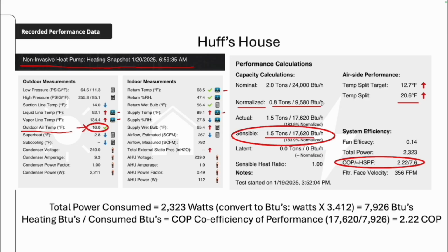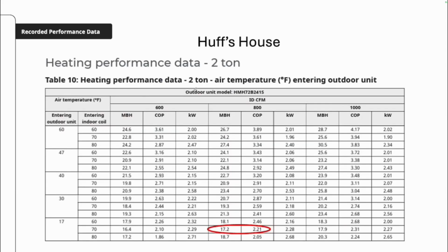And so this is why I'm doing this video. This is why we're talking about literally going back to the OEM's documents. So I'm delivering 17,620 BTUs to my house. Now, my return temperature is 68.5. My thermostat was reading 70. There's a little bit of distance between the two. And I also found out why it's reading 68.5. I did have a little bit of air leakage coming in from where this mechanical closet was, and we got that figured out. But still, this delivered capacity is correct.